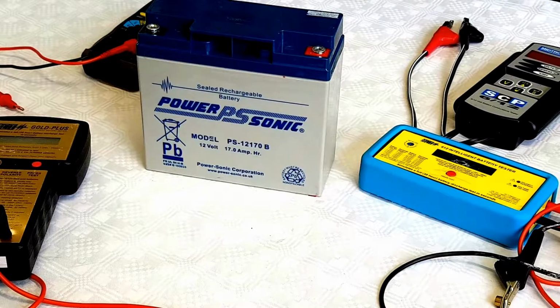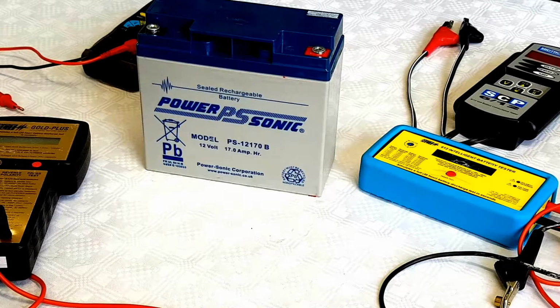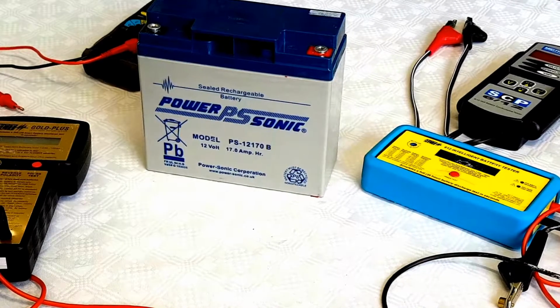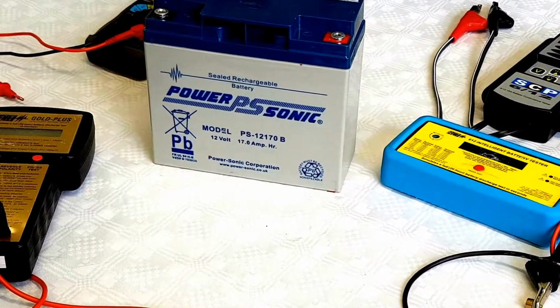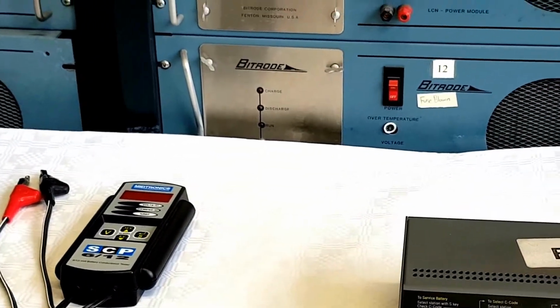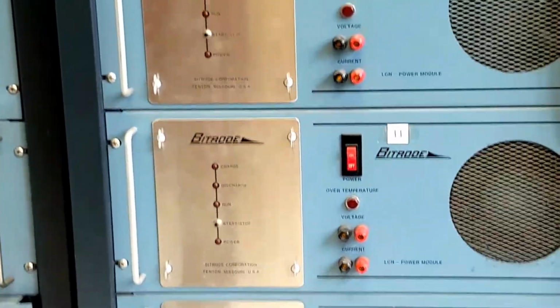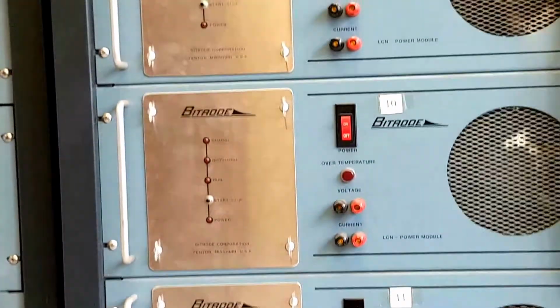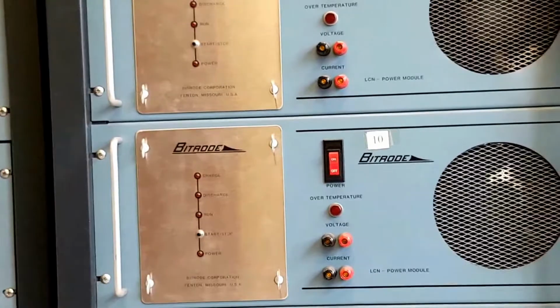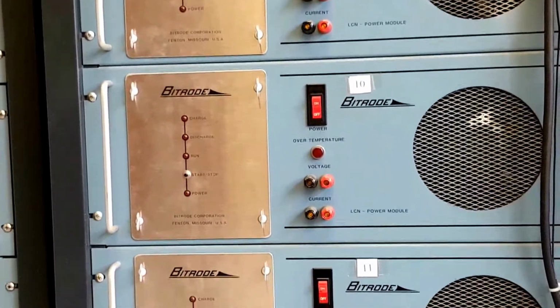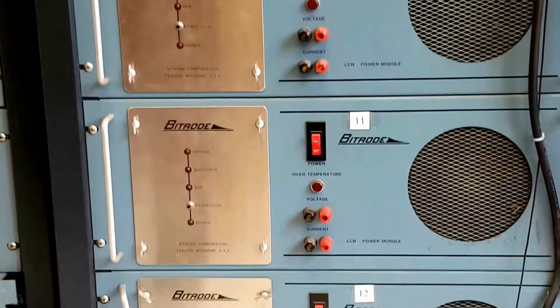First of all, I'd like to emphasize that there is no way other than to do the time-honored discharge test to measure the true amp hour capacity of a battery. The static laboratory tester designed to test for amp hour capacity is the Bytrode LCN 1250. These are the blue testers that you can see right there, and these circuits will test batteries up to 1000 amp hours.